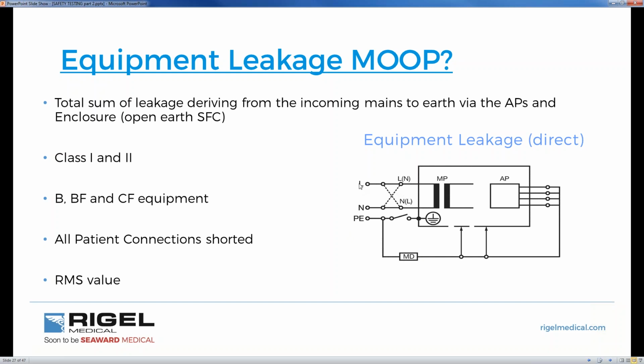So if I was to measure any earth leakage, again, I'll use the same example. If the total system is 100 milliamps, 1 milliamp will go missing because of all the stray capacitance and dielectric resistance within our medical device. So if you have 99 flowing between live and neutral to provide power, 1 milliamp must go missing. Where does it go missing? It will flow through the combined connections through our measuring device, our 1K body model, back to protective earth. And that's what we're measuring.